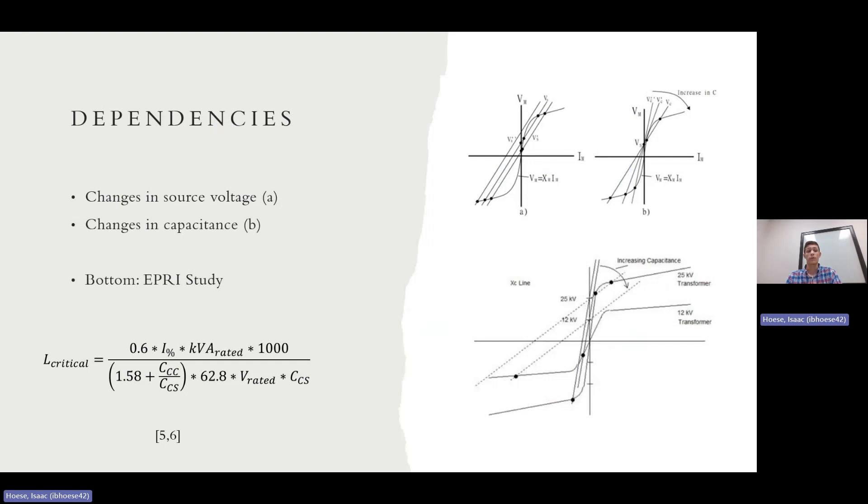So if you know all those values, which you should, you can get the critical length of your underground cable. And once you reach that length, that critical length, you're in the threshold for ferroresonance to begin.